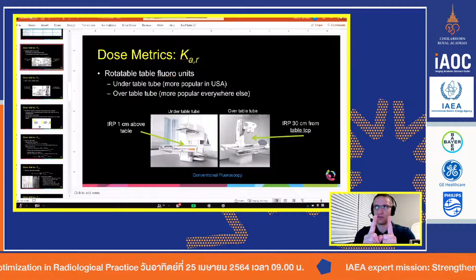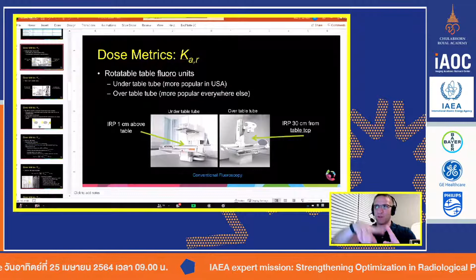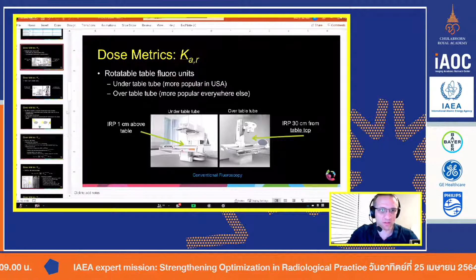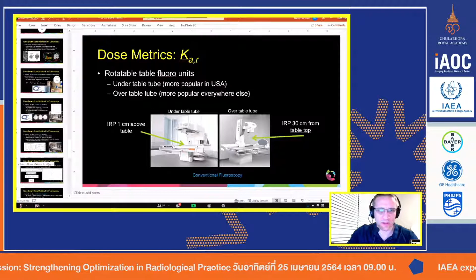So the beam that's coming out of the X-ray tube at the center, so you're basically putting it here, let me pull this down. And right there. So let me look at a little bigger. This chamber right here is actually the small one. We call it a Farmer chamber. And because it's small, it really doesn't matter if my field of view is big or small. It just doesn't matter. So that's why I use a smaller chamber, maybe you could even do smaller if you want. Not a 15 cc, excuse me, a 0.15 cc or 0.3 cc.